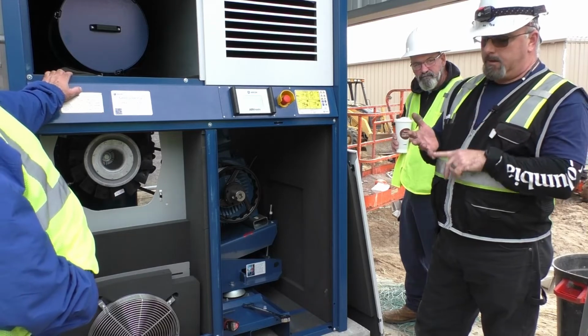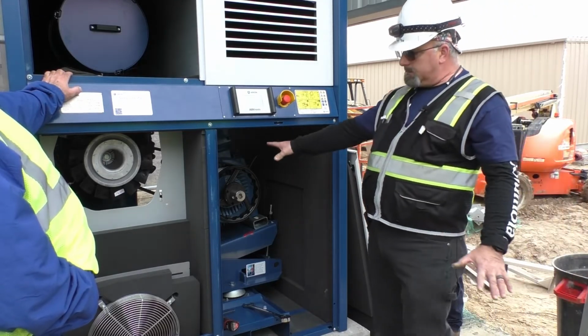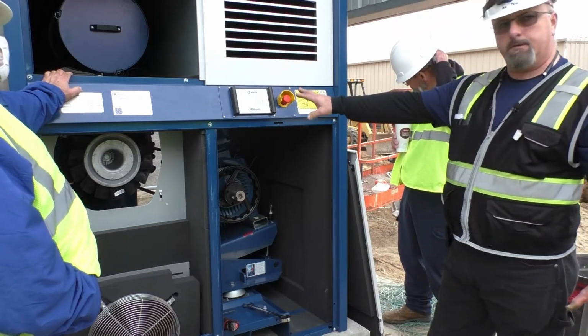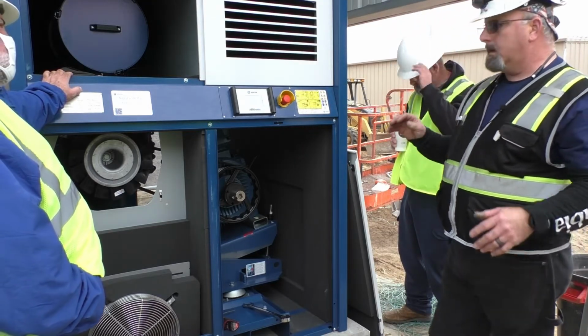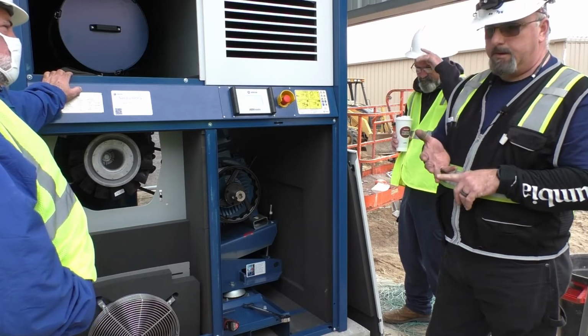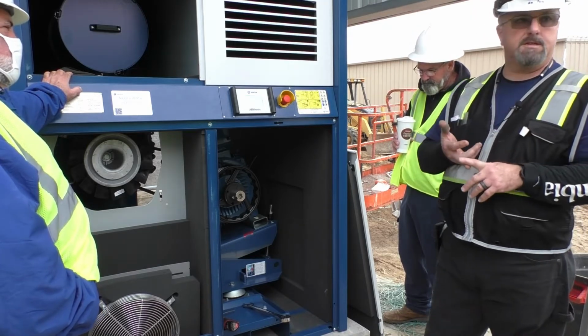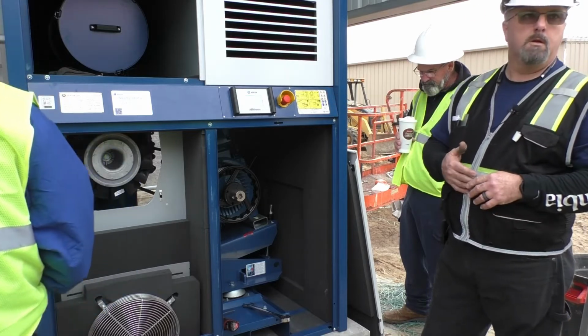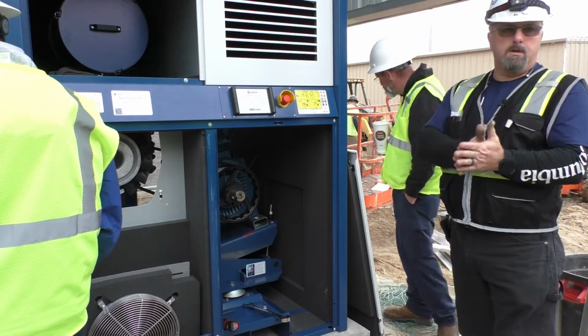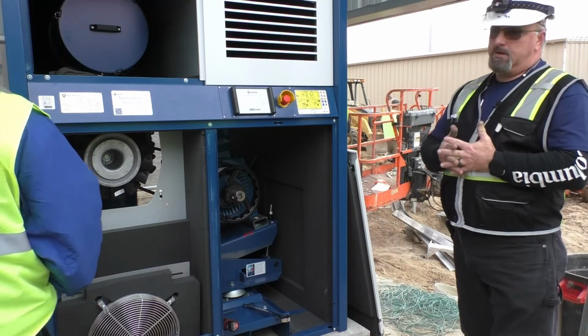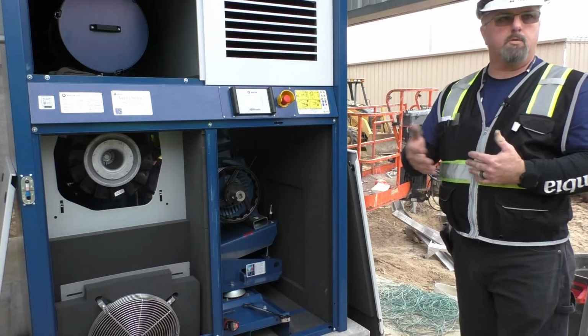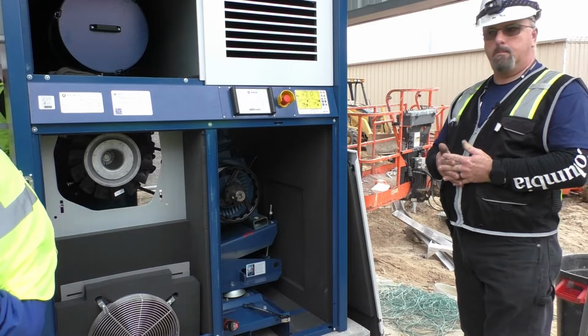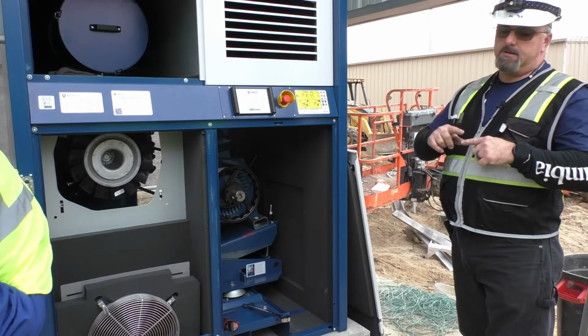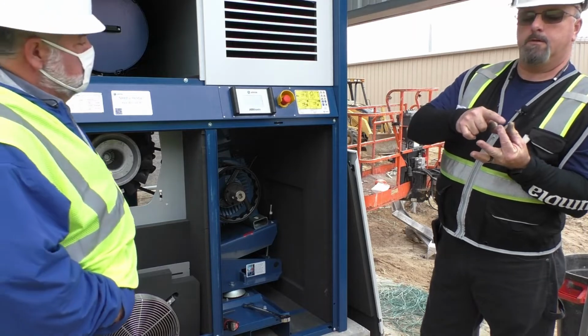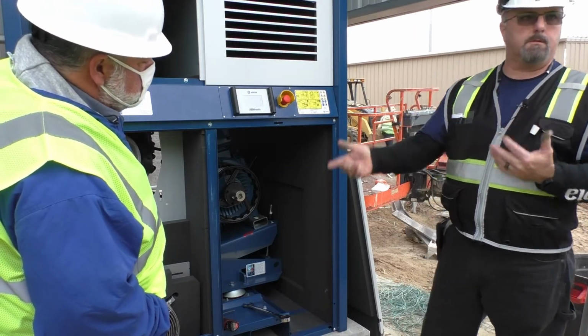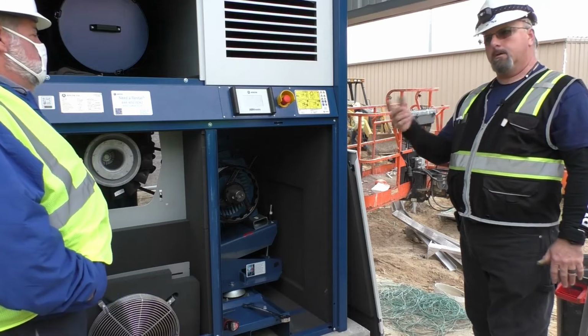You can start getting excess belt wear. You'll start seeing a lot of belt dust on the front of the motor, potentially the front of the blower. It can also cause premature belt failure, and it can also cause sheave wear, because it's pulling against one side or the other. And we have seen in severe issues where it has actually caused the belt to walk off the pulley, because you're pulling on one side and it reaches a point to where when it's sitting in that groove, it walks up on top, and it can either flip over or come completely off.